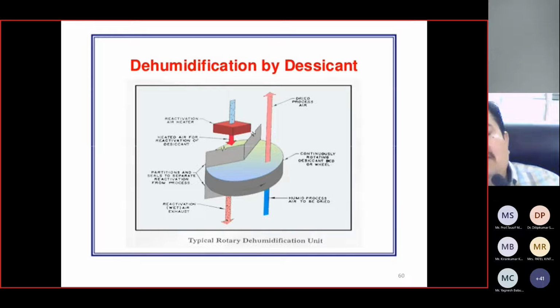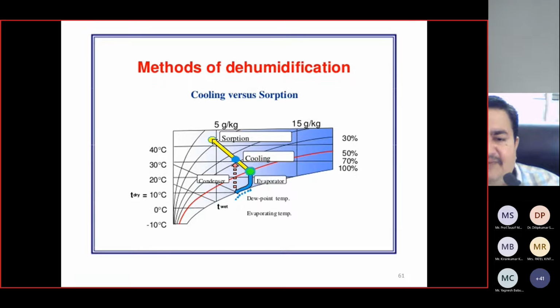The hot air temperature is achieved by passing the reactivation air, prior to flowing through the dehumidifier, through a primary heater, or you can say an electric heater, or solar based air heating coils. So there are diversified sources of energy to heat the reactivation air. There are different methods of dehumidification. Either you can achieve it by the dew point or by getting a temperature, as mentioned, by sorption and cooling.